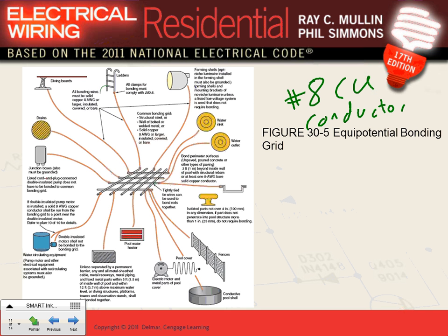The rebars, if you're building, these rebars, guys, 12 by 12, they bond the whole bottom of the swimming pool as well as the belly of the swimming pool. So if this is the swimming pool belly, all this will be rebars also bonded here, and/or copper conductor number 8. They make a grid. The whole swimming pool is all bonded with a grid. And that grid, bottom and sides, everything else will be bonded to it. Can you give a thumbs up, Chad? We understand that? Number 8? Okay. Really not rocket science to it.